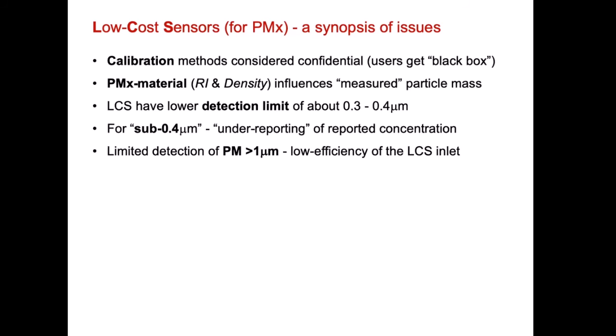Then there's the question of the lower detection limit, the sensitivity. Usually low-cost sensors stop measuring between 0.3 and 0.4 micrometers. That means if we measure PM2.5, we are losing particles at the low end. Remember from one of my first slides, the small particles have little mass. So one could think, if we have little mass, maybe it doesn't matter that we can't count smaller than 0.3. But if the other instrument measures only up to 0.4 or 0.5, well, then we may have a problem.